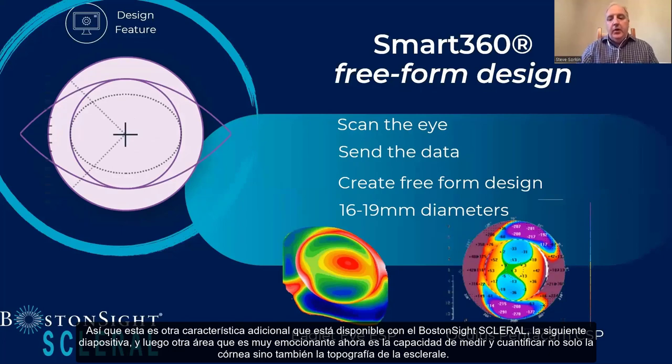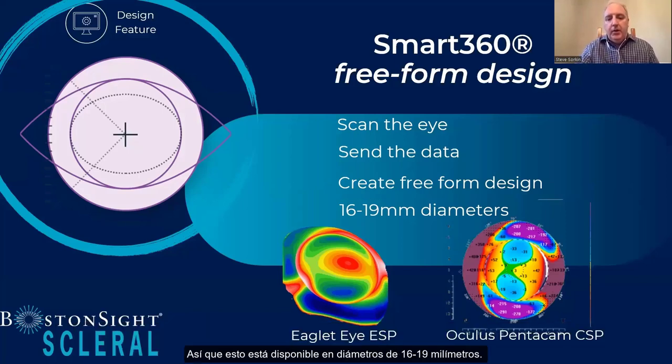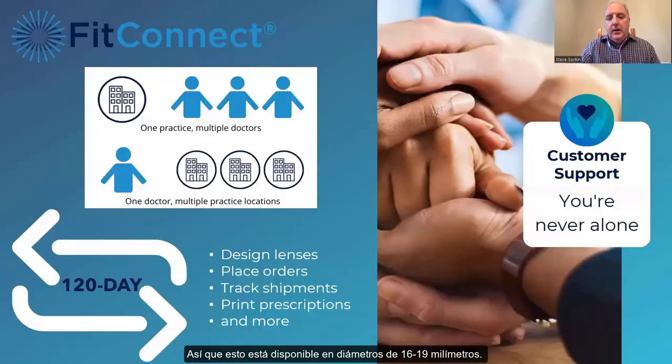Another exciting area is the ability to measure and quantify not only the cornea but also scleral topography. There are two different instruments — the Eaglet Eye ESP and the Oculus Pentacam CSP — which can be incorporated into your practice to allow more of a free-form design: a more customized lens rather than using only diagnostic lenses. This is available in 16- to 19-millimeter diameters.